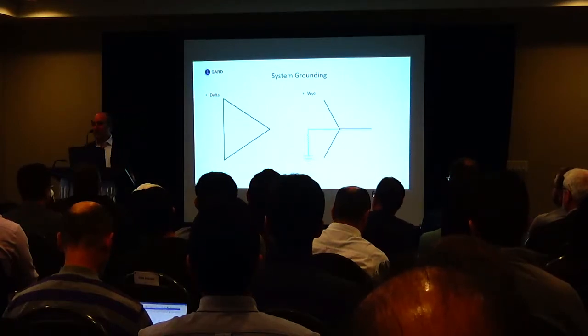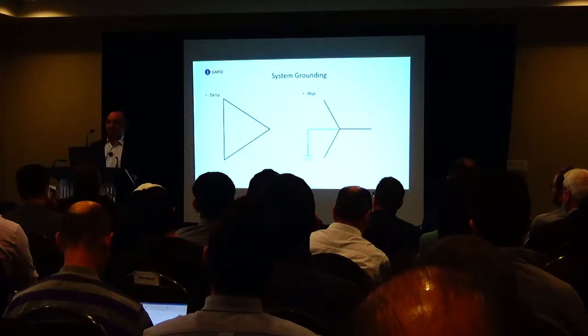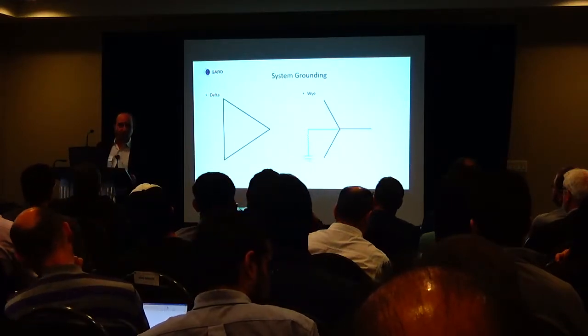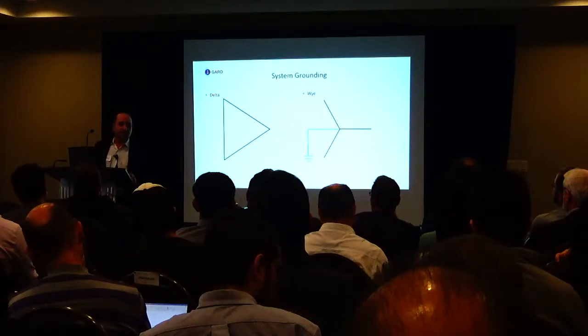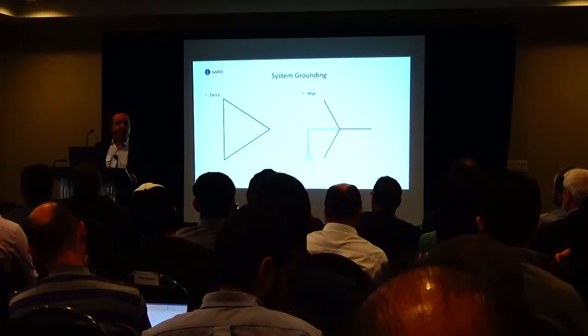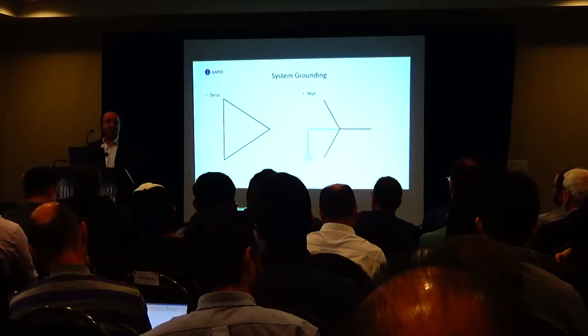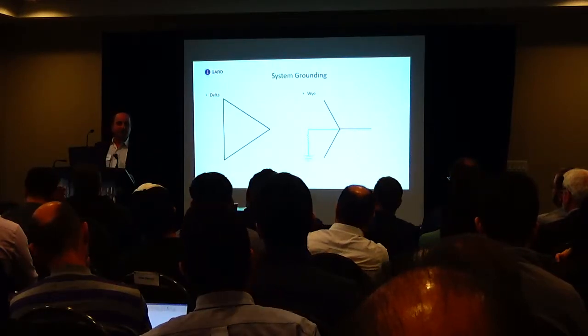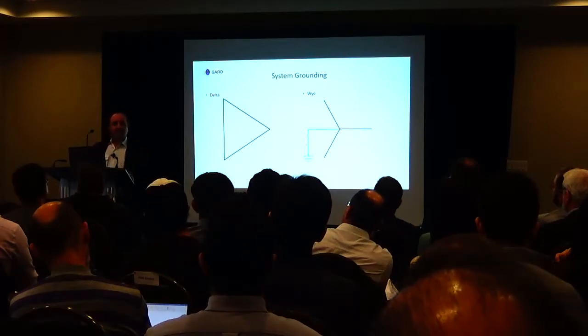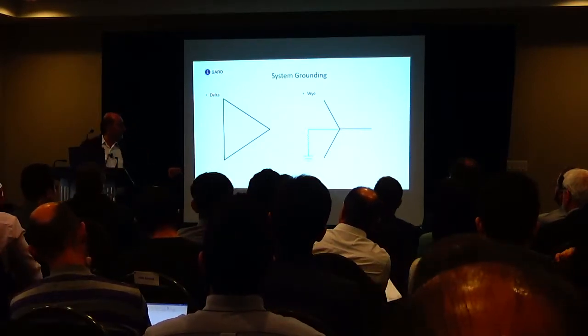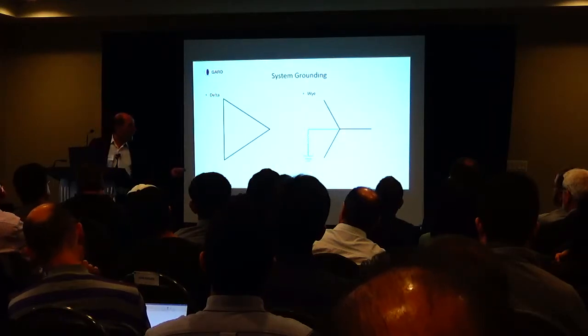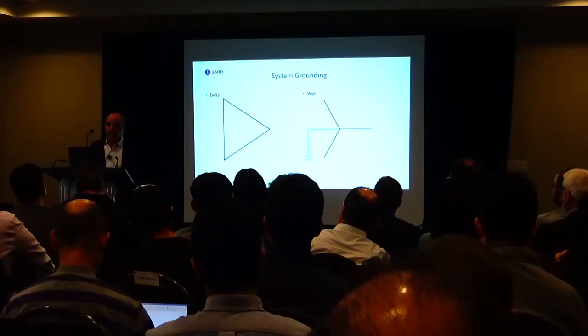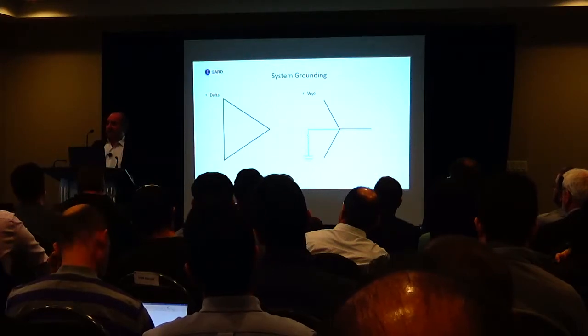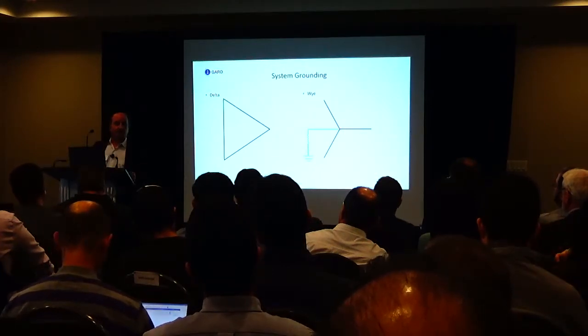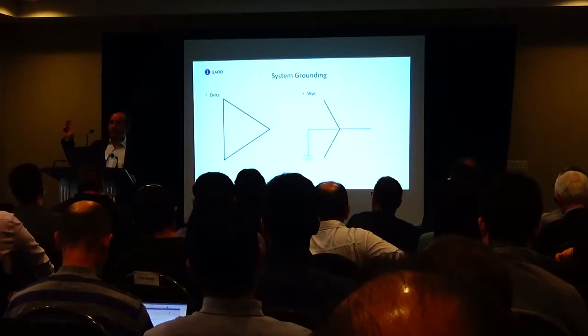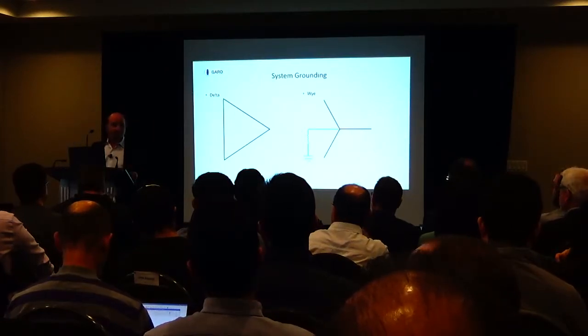The difference between a low and a high resistance grounded system is the amount of current that we have flow through the system. If you limit your fault current, on a system that's less than 5 kV, to 10 amps or less, it's a high resistance grounded system. The benefits of a high resistance grounded system: for example, you have a 600 volt system, you put a 69 ohm resistor there. You limit your fault current to 5 amps. You don't have to trip. Canadian Electrical Code, the National Electrical Code, who does work in the States? You do it. You don't have to trip.